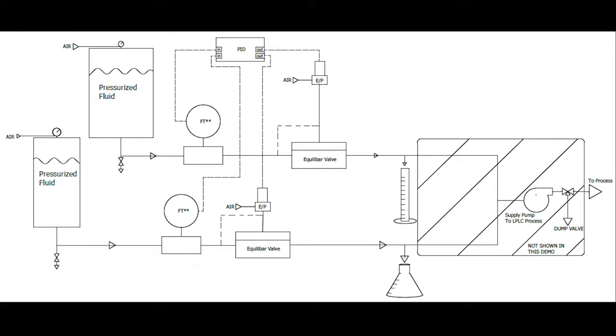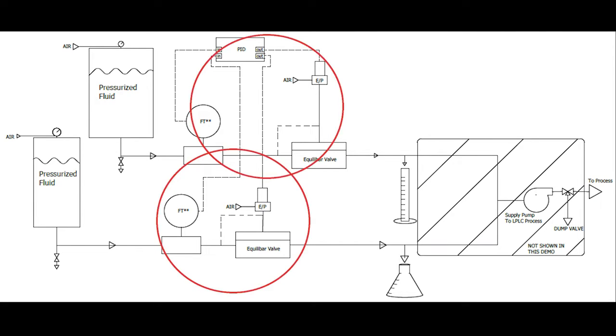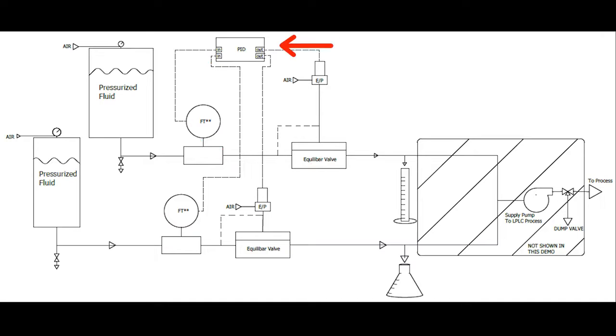Each of these FDO4 valves is set up in a control loop, with the flow transducer sending a signal to a PID controller. This PID controller monitors the flow from the flow transducer and checks it against a process set point. It then adjusts the signal to an electropneumatic valve, setting the pilot pressure to the Equilibar FDO4 based off of the process set point.